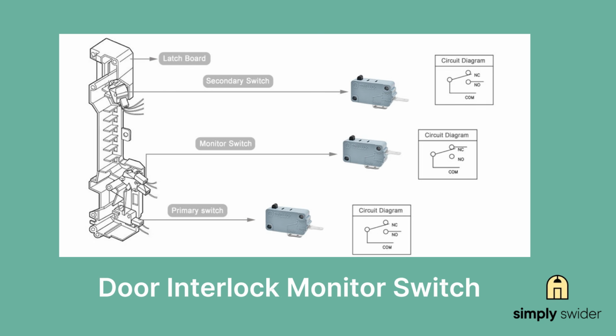So the number one cause I see, and this is probably 40 to 50% of the breaker tripping calls I get, is that monitor switch in the door interlock system. Now here's what's actually happening. There's this little switch called the monitor switch that's designed to short out the power line if the primary door switch fails. It's a safety thing. But when it goes bad, it creates an instant dead short that'll trip your breaker faster than you can blink.